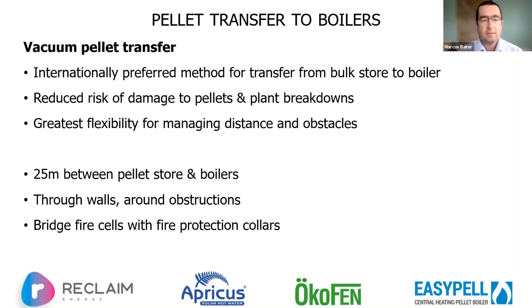The standard onboard transfer system would normally be 25 meters between your pellet store and your boiler. And we can go through walls and around obstructions and bridge fire cells with fire protection collars that close up automatically in case of temperature.